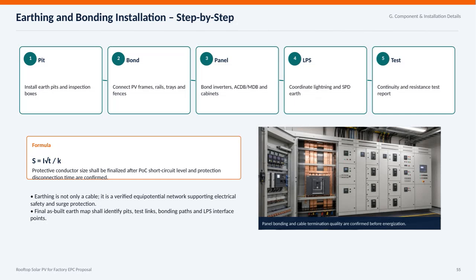Let's go through the earthing and bonding installation steps for the rooftop solar PV system on the factory EPC proposal. First, we start by installing earth pits and inspection boxes, which are fundamental to establishing a reliable grounding network. Next, we bond all the PV frames, rails, trays, and fences to ensure they are at the same potential, preventing any dangerous voltage differences. Then, we move on to bonding critical electrical components such as inverters, ACDB, MDB, and the cabinets to secure the entire electrical system. Lightning protection systems and surge protective device earth connections must be coordinated carefully to maintain system integrity during transient events. Finally, we conduct thorough continuity and resistance tests to verify the earthing system's effectiveness.